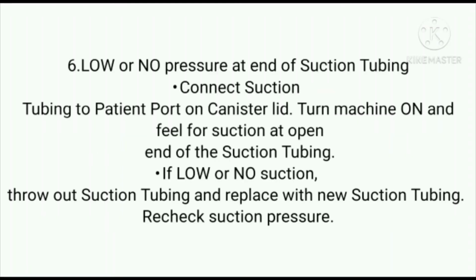Lastly, low or no pressure at end of suction tubing. You must connect suction tubing to patient port on canister lid, turn machine on and feel for suction at open end of the suction tubing. If low or no suction, throw out suction tubing and replace with new suction tubing. Recheck suction pressure.